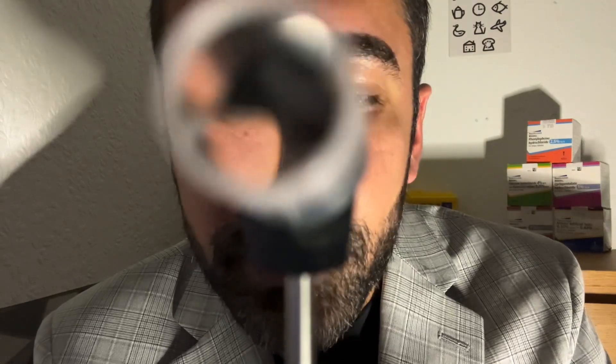This is housed on the slit lamp. We ask the patient to keep both eyes open, look at one point in the distance, and breathe normally. We use the blue light from the slit lamp — it excites the dye, allowing us to visualise the mires. We bring it close to the eye, ask the patient to blink, then rest very delicately on the epithelial surface. Look through the slit lamp, align the mires, come back, ask the patient to relax, and then take the reading off the scale.